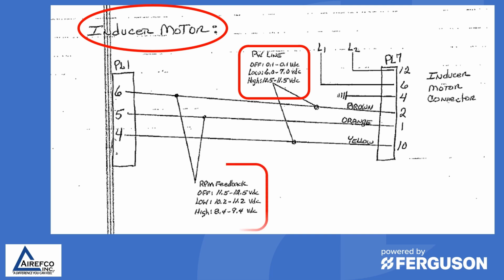Then this inducer motor has a feedback line to tell the board what RPMs it is running at. So in the off cycle, you should have 11.5 to 12.5 DC, low 10.2 to 11.2 volts DC, and high 8.4 to 9.4 DC.